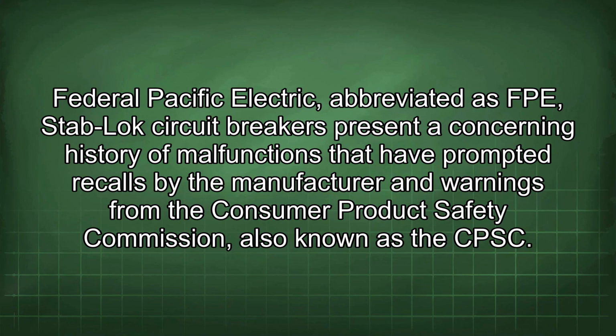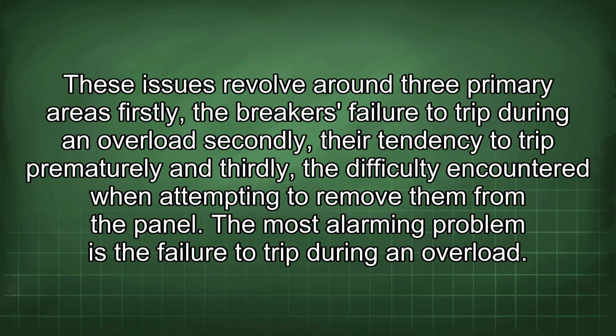Federal Pacific Electric, abbreviated as FPE Stab-Lok circuit breakers present a concerning history of malfunctions that have prompted recalls by the manufacturer and warnings from the Consumer Product Safety Commission, also known as the CPSC. These issues revolve around three primary areas. Firstly, the breaker's failure to trip during an overload. Secondly, their tendency to trip prematurely. And thirdly, the difficulty encountered when attempting to remove them from the panel.